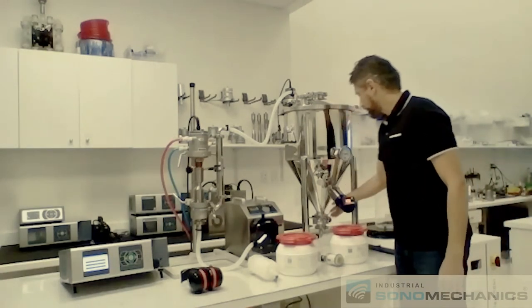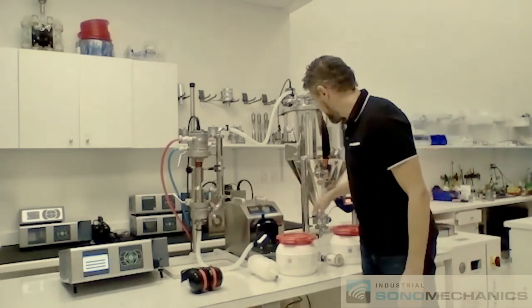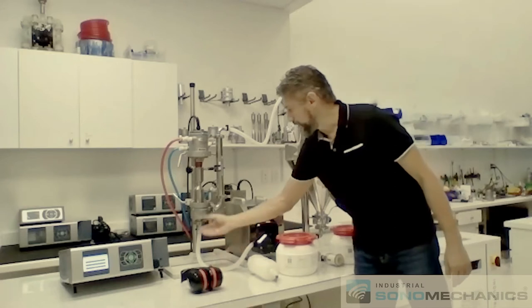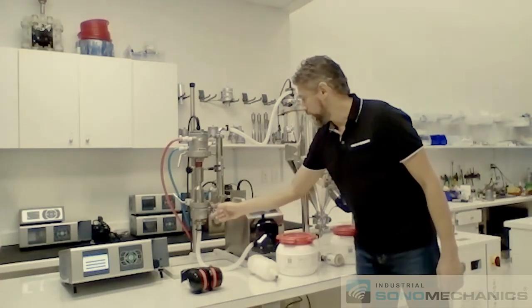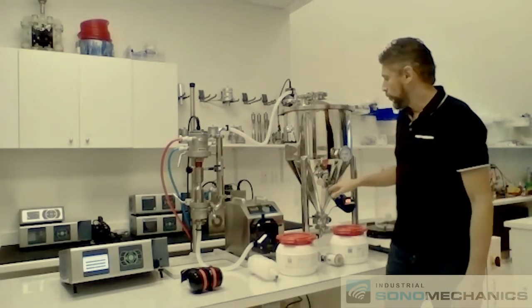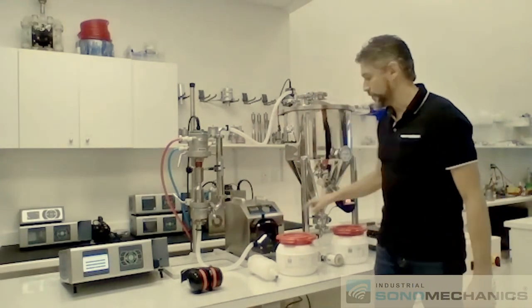you will open up this valve and start the pump, which will take the premix into the reactor chamber, out this side, through the heat exchanger and back into the tank. This is your loop.